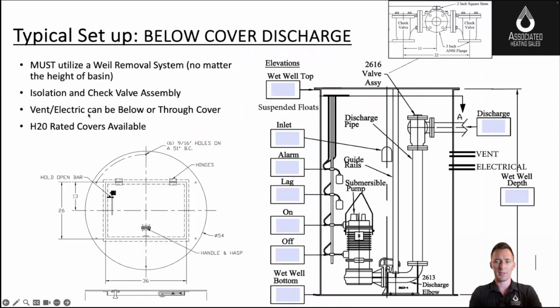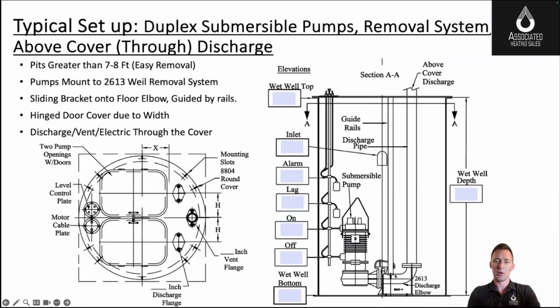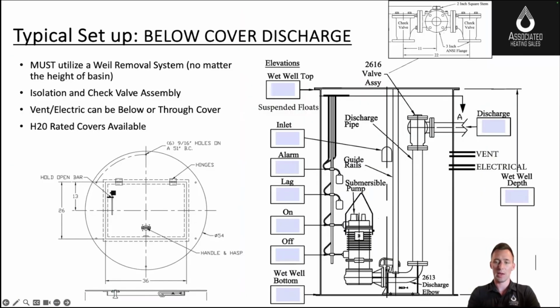The other nice item that you saw in that video, let me start this, is the valve assembly. So here's your drawing. Let's go back one. This is the drawing of the rail system in a deep pit indoors. You're still running the discharge pipe through the cover and the vent. This is the more common scenario where you have either a deep pit or an outdoor pit or an area where you need a flush cover. This could be vehicle rated cover, vehicle rated hatch, concrete over it, or it could just be your standard cover in an indoor area where people are going to walk over it. You're not in that mechanical room where you can get away with piping coming up through there. So this is what that drawing looks like.